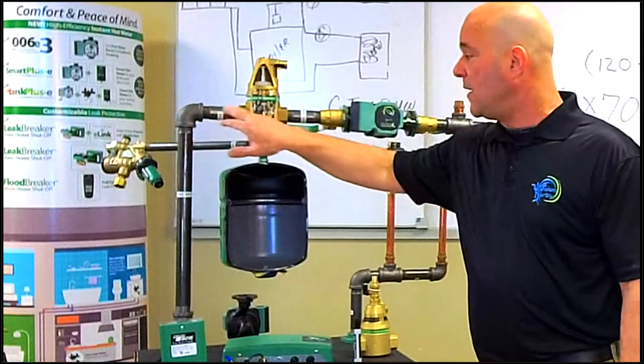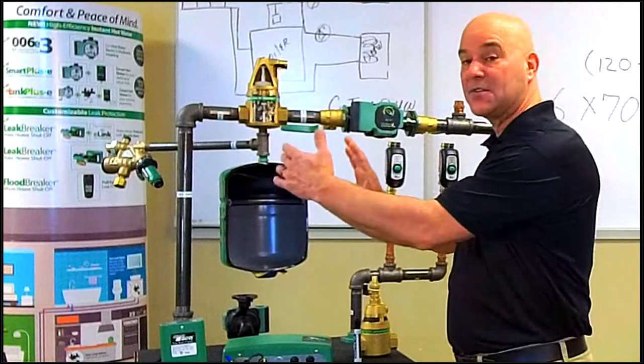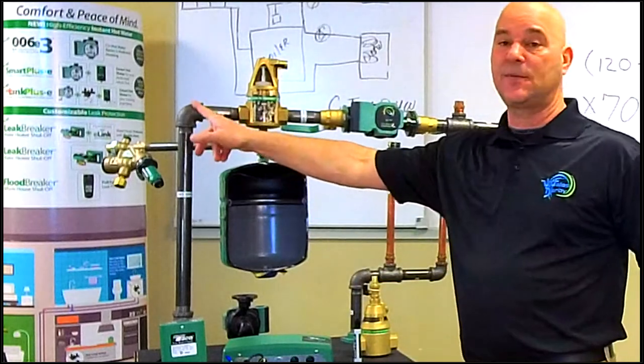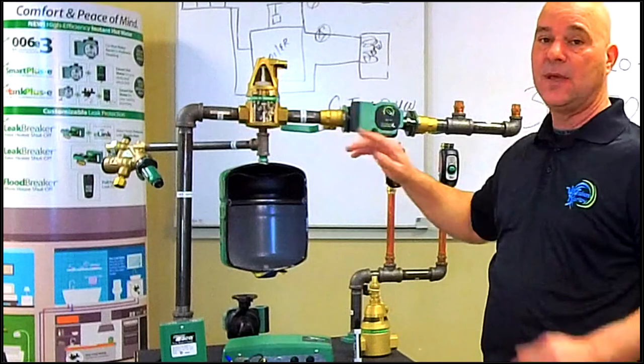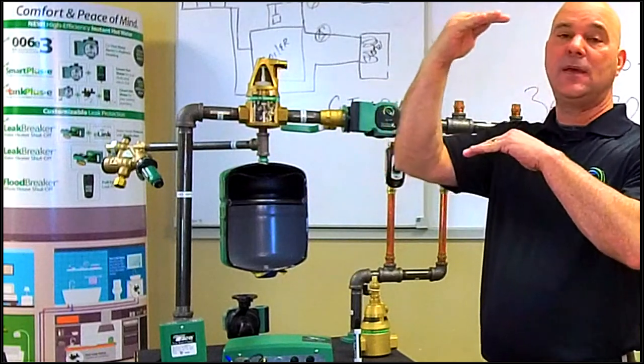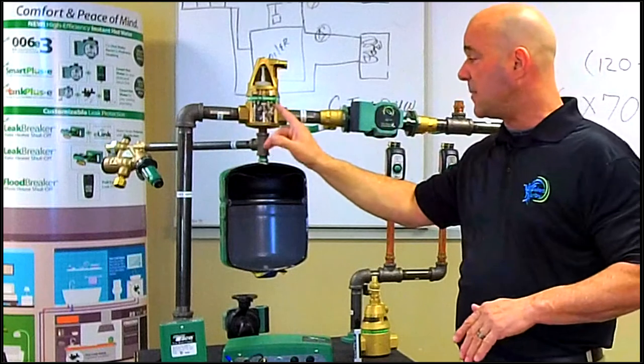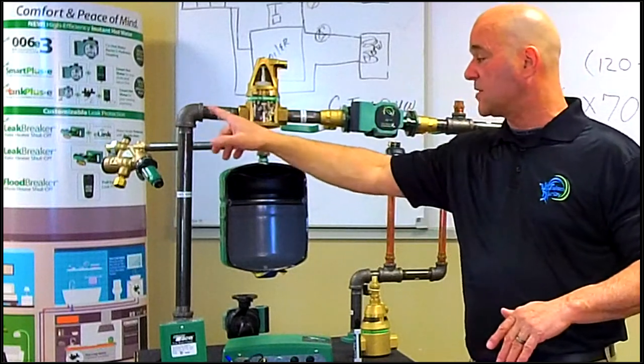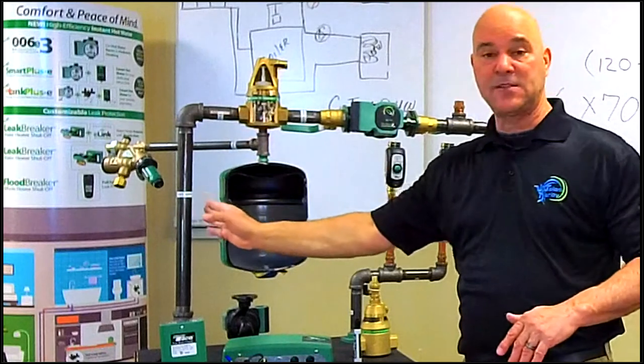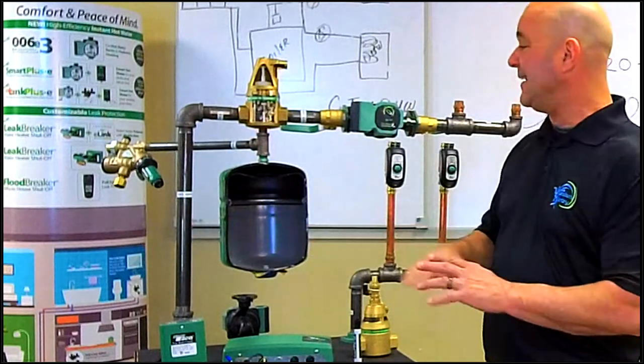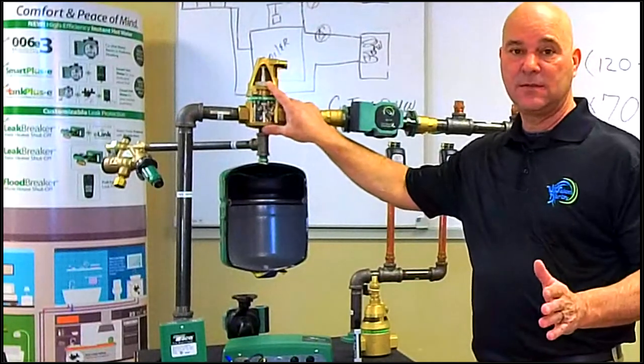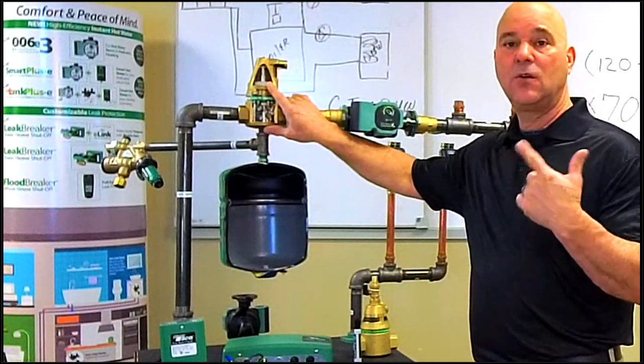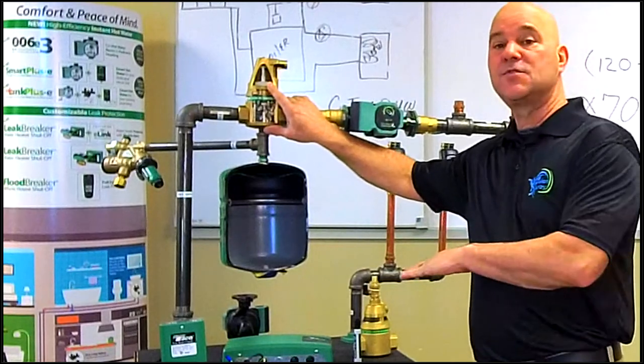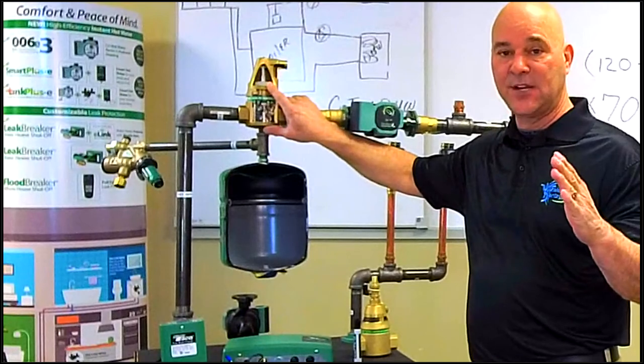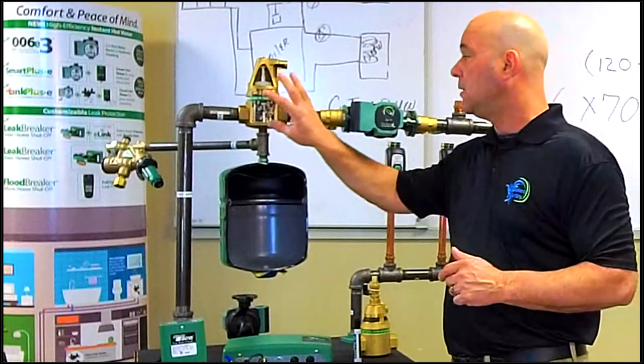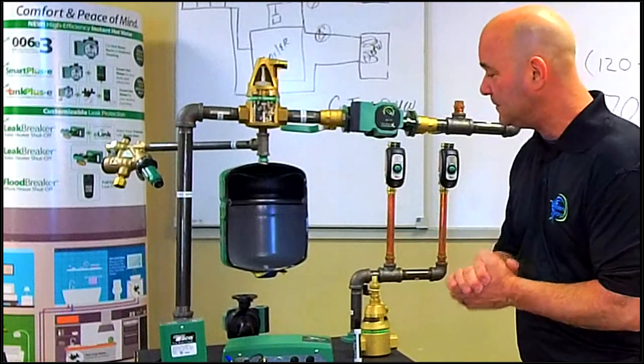Okay, so no minimum distance. If this were a cast iron air scoop, you need a minimum of 18 inches from your closest elbow to that cast iron air scoop. That allows the air to work its way up to the top of the pipe and then expel it from the system. With these air separators, there's no minimum distance. Most guys will go just large enough on this nipple to fit their expansion tank. If you're doing any type of condensing equipment, these are a must, because you don't want a supply sensor or a return sensor to read a superheated air pocket as it goes through the heat exchanger and throw you into an error code. So these are a must when you're doing condensing high efficiency equipment.